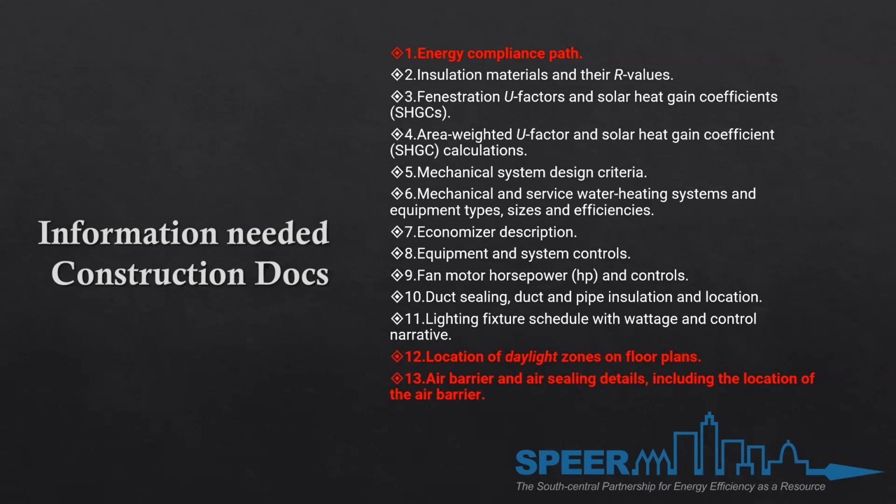And that normally will always take at least 2 different options to get you to 10 or more points based on your climate zone. If you do 10% cooling efficiency improvements in climate zone 1, you're probably at 10 points and you're already there and you're done. But if you're in climate zone 3, you're going to get maybe 6 points, maybe 8 points, and you're going to have to add another option to get you over that hump of 10 points. So yes, they are required. And then insulation, that's still the same.